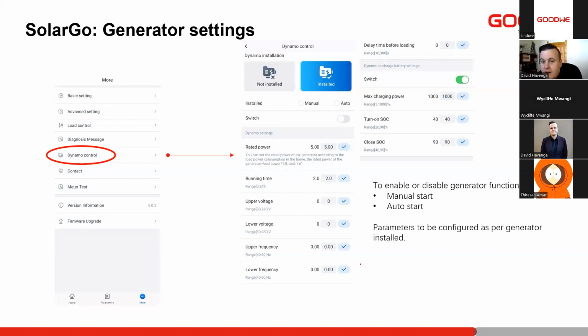So if the inverter has a voltage on the grid input and the smart meter is off, it will then presume that a generator is running. It's very important to keep that in mind. Here you can select the rated power of your generator that's connected to the device. If the generator is slightly smaller than the inverter, which is not recommended, you can set that there.